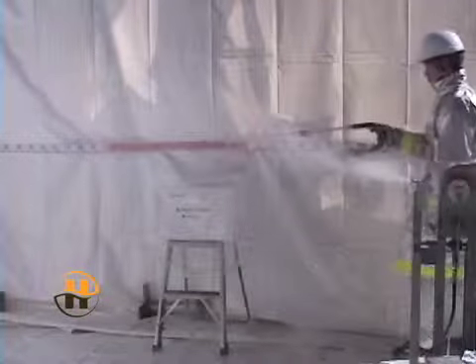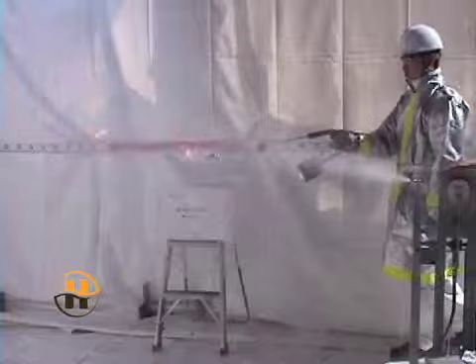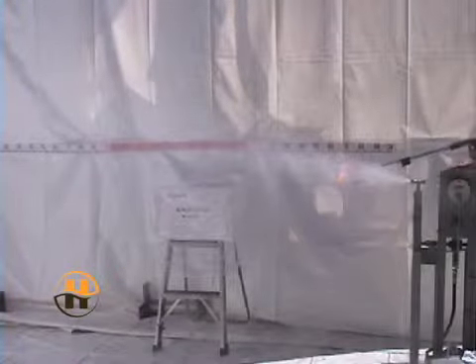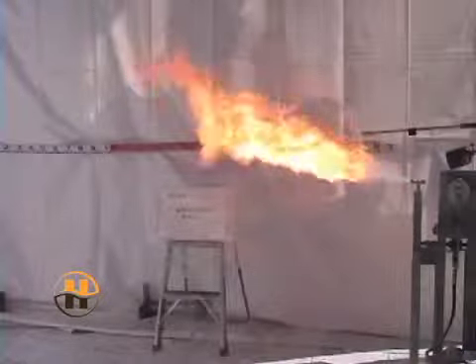This is a petroleum oil-based product. As you can see, there is an intense flame that occurs when the propane torch is introduced into the atomized spray of petroleum oil. The oil continues to burn until the fluid spray is shut off.